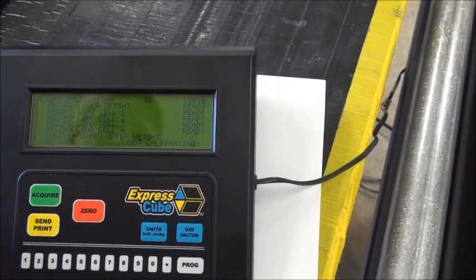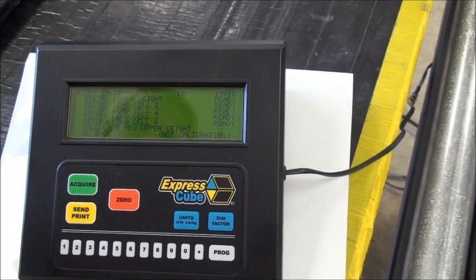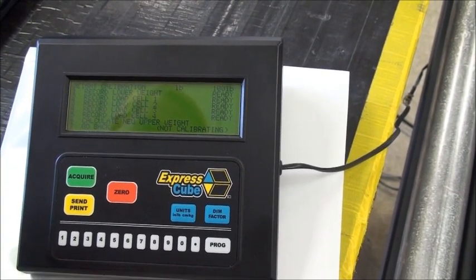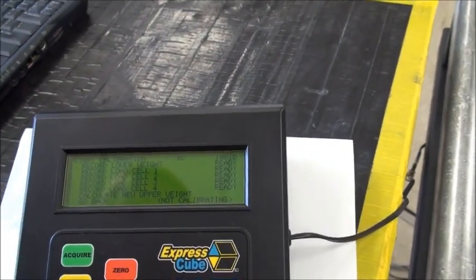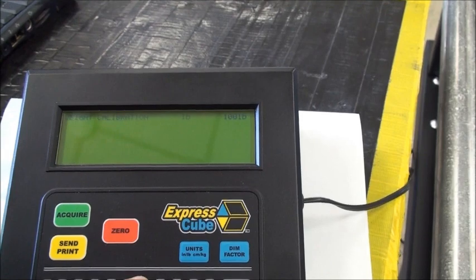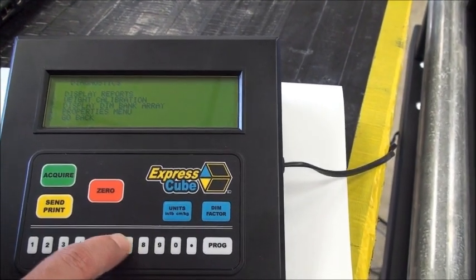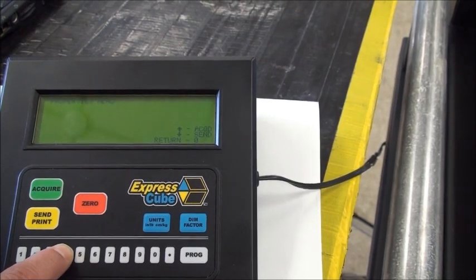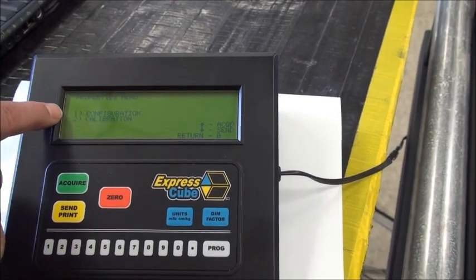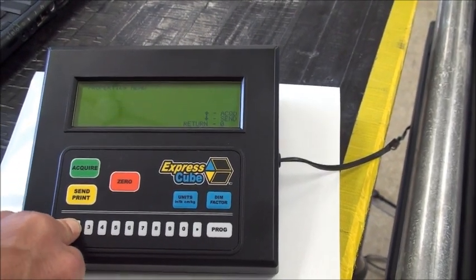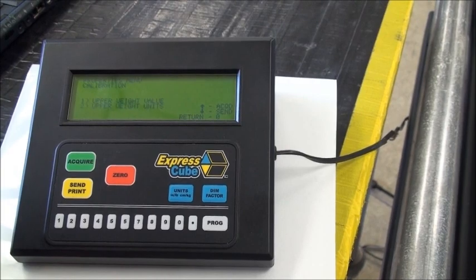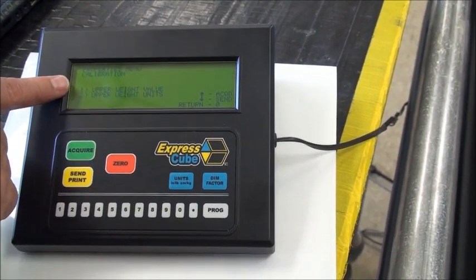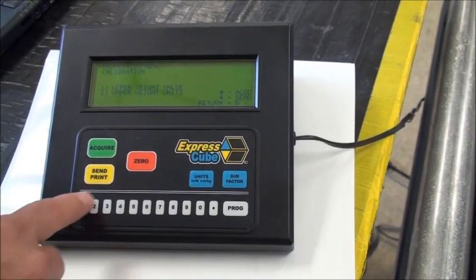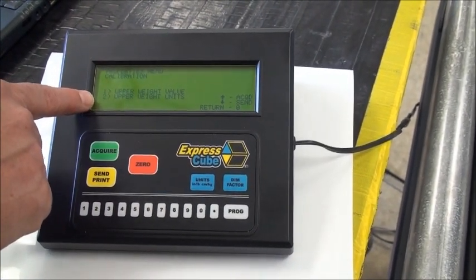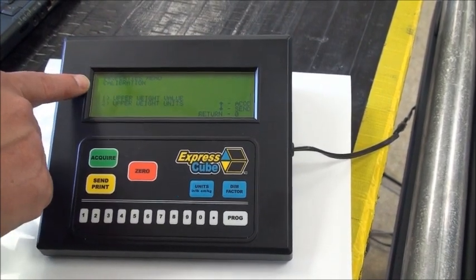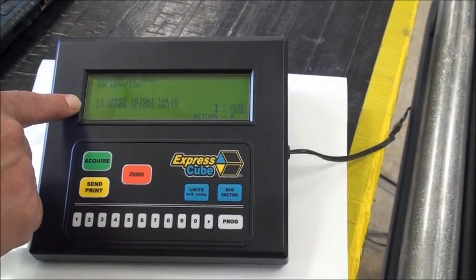Now let's suppose I only have 50 pounds, or I'm working in kilos. What I can do is come back out here, which says 7, go back, and actually I go into the properties menu, number 4 here. From there I go into number 2, which says calibration. Now you'll see a list come up here. The upper weight value and the upper weight units are the two where I want to set exactly what it is I'm going to be calibrating to.